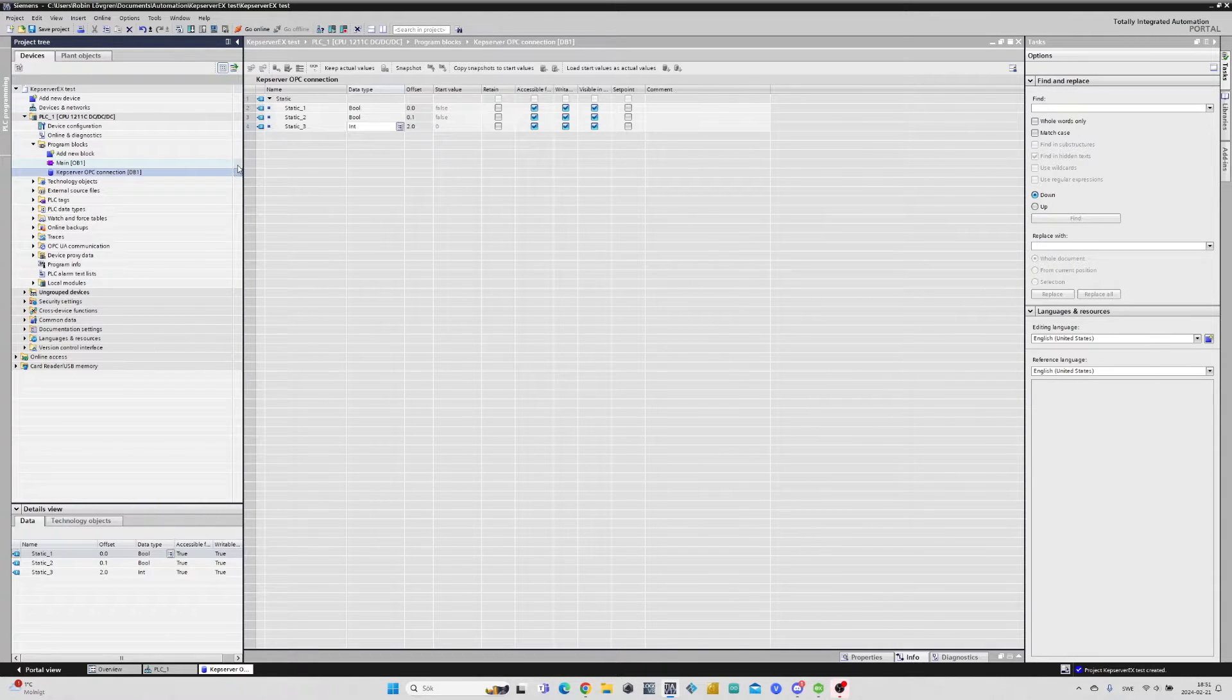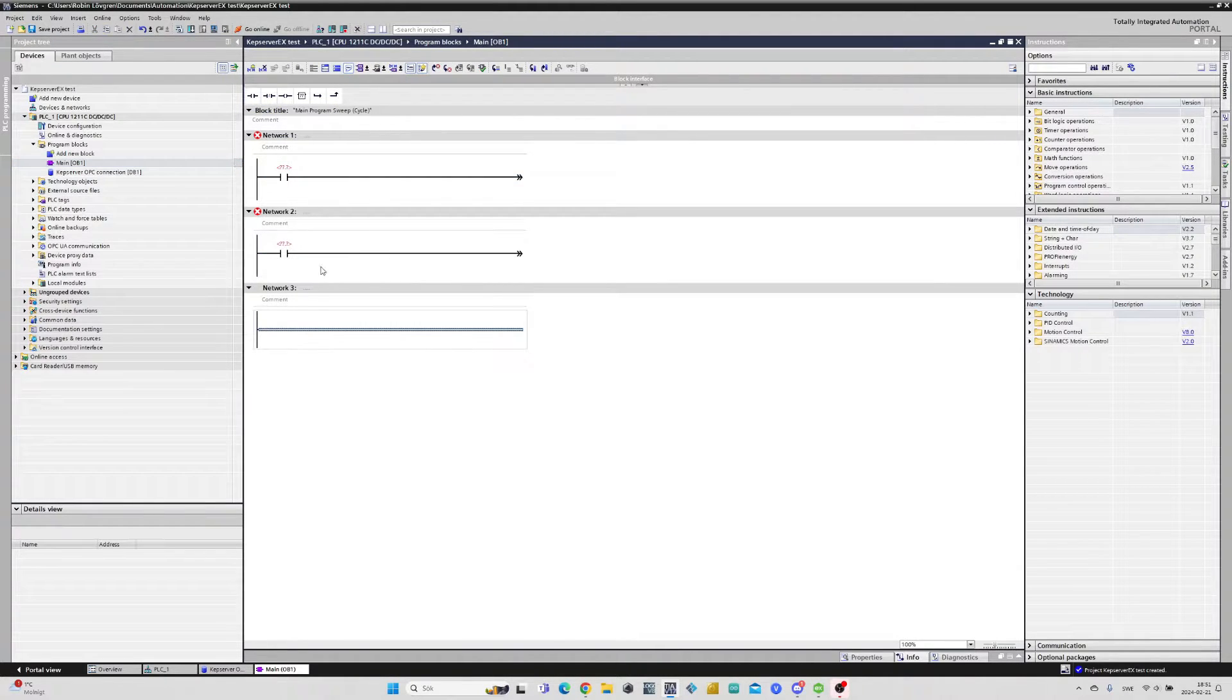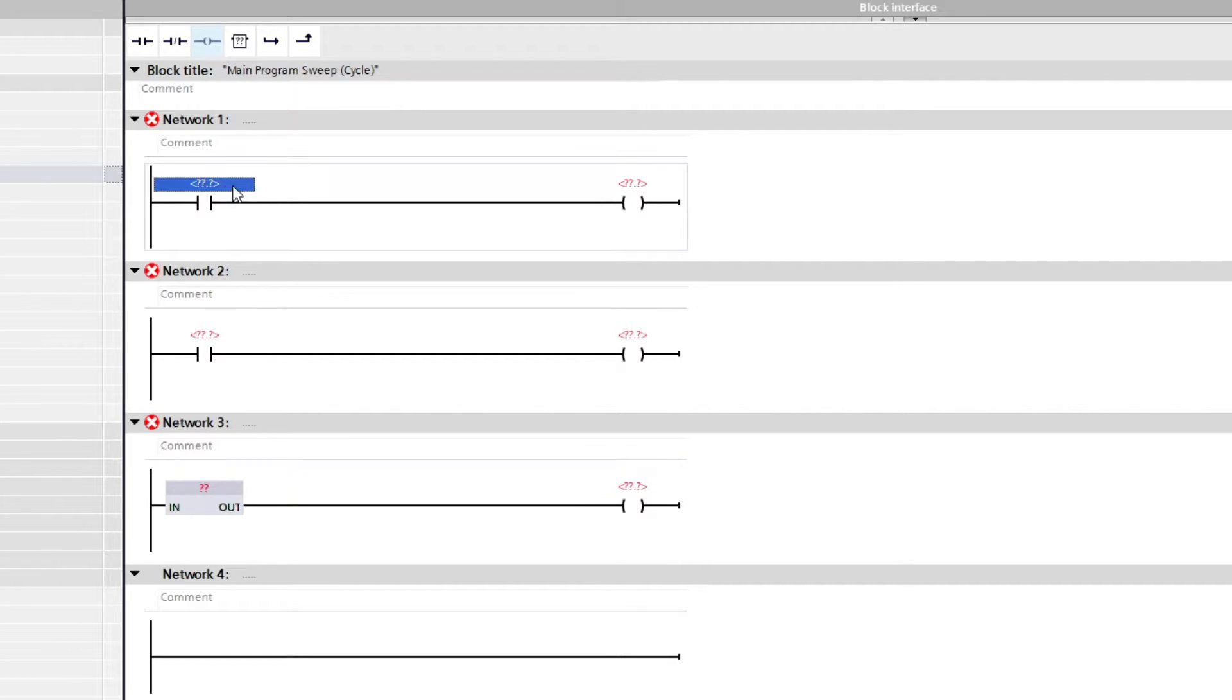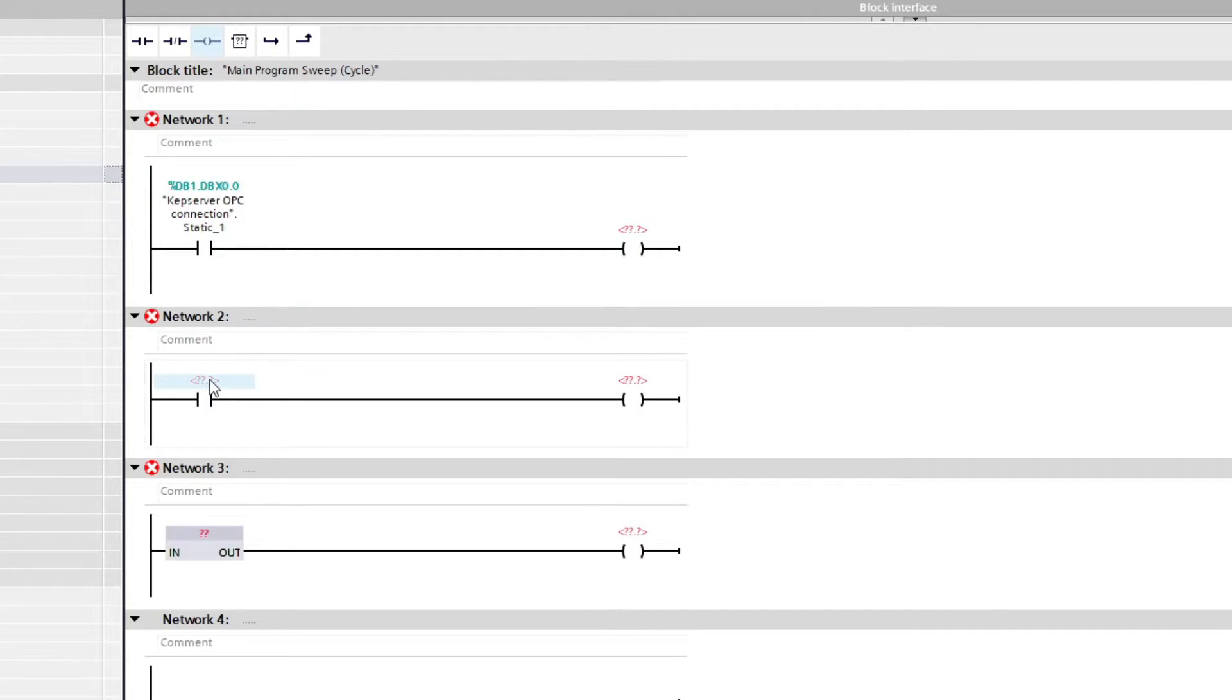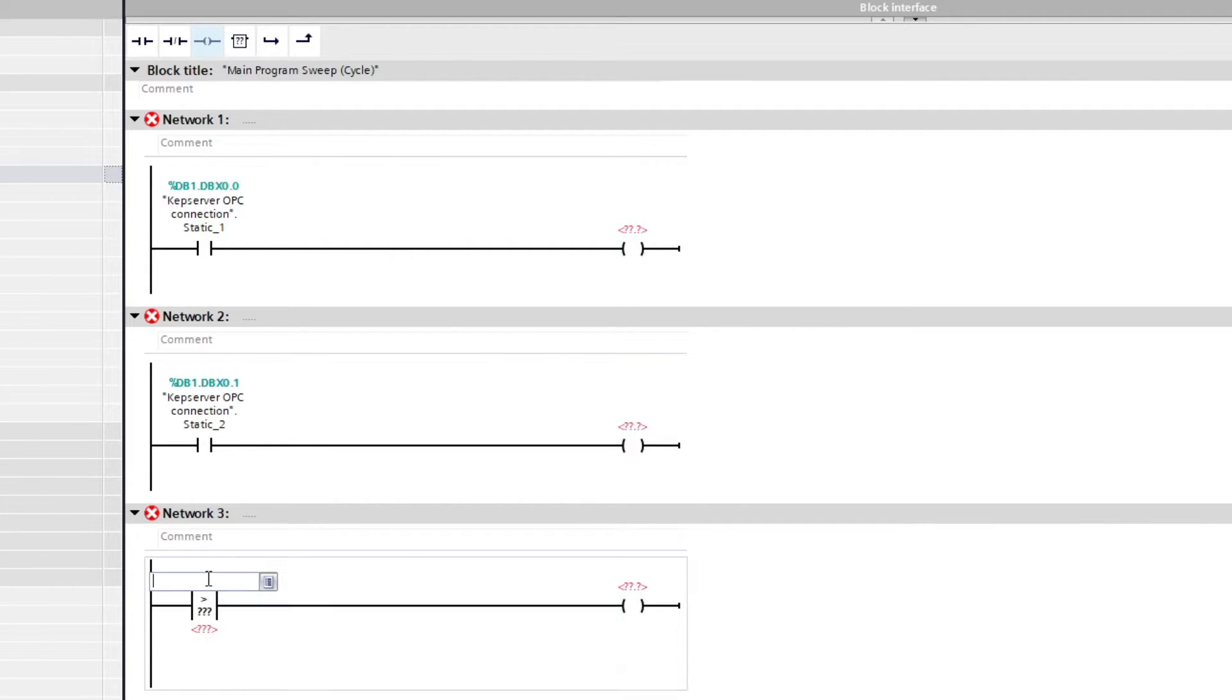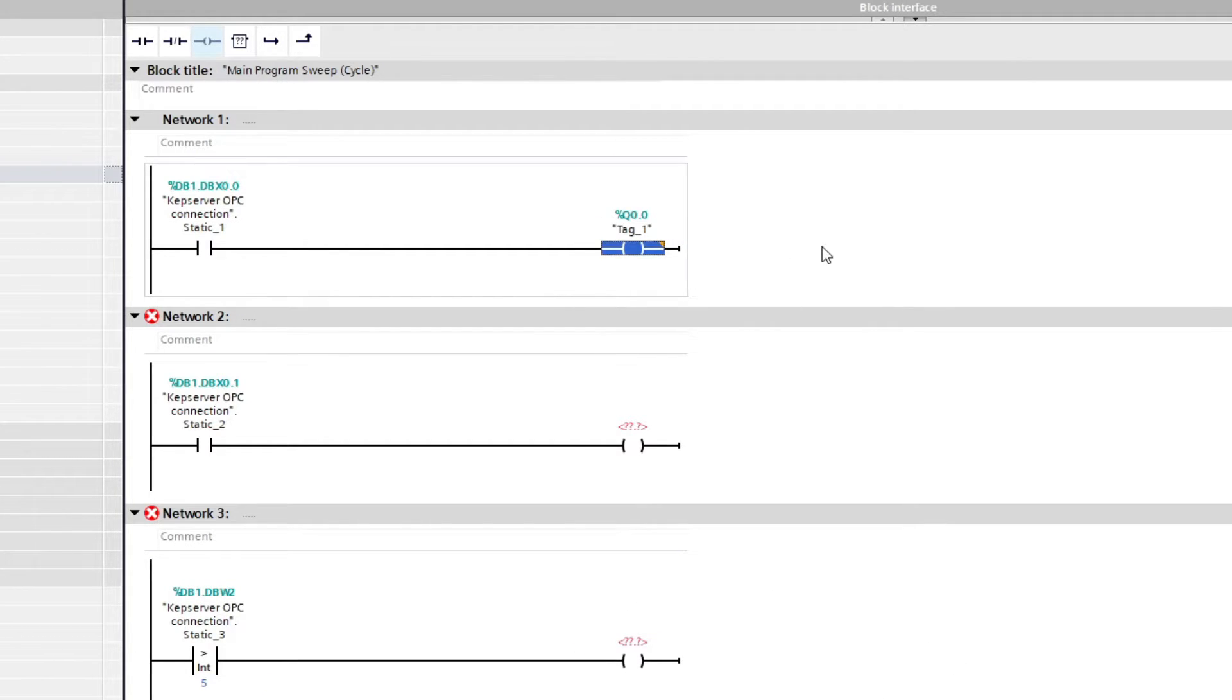I will now open up our main block and do some simple programming. To add our data block tag to an input we need to click on the question marks above. Then we open up the list and click on our data block. Then we click on which tag we want to add. As you can see now all our tags have an address. For example our first tag has been given the address DB1.DBX0.0. I will just keep the code simple and connect each tag to an output on my PLC.